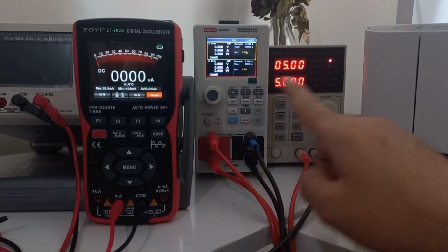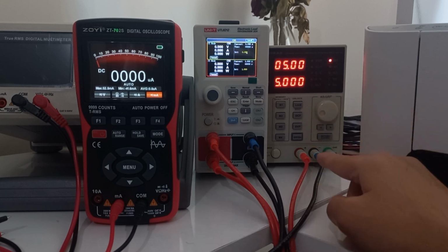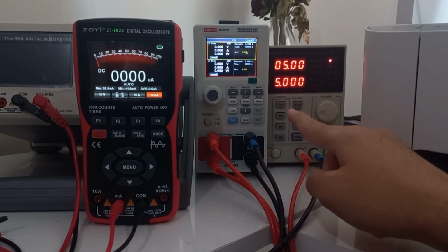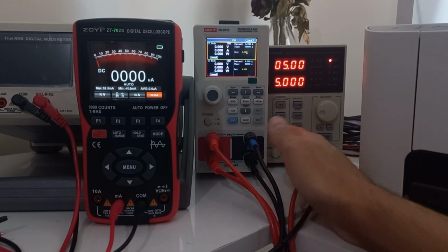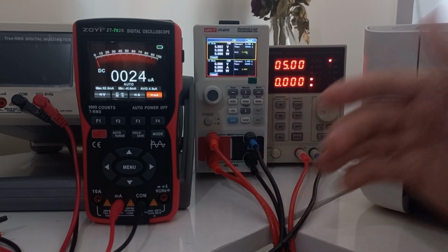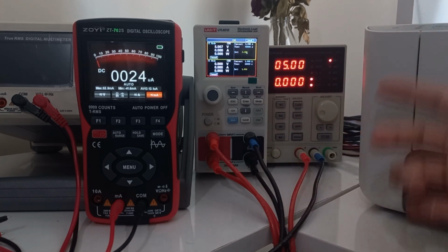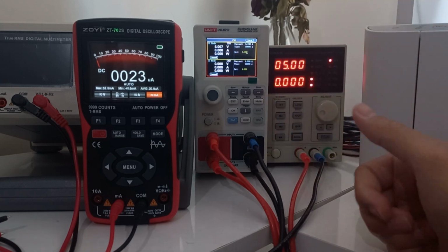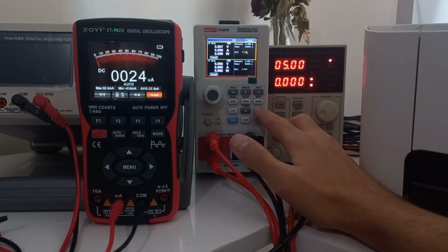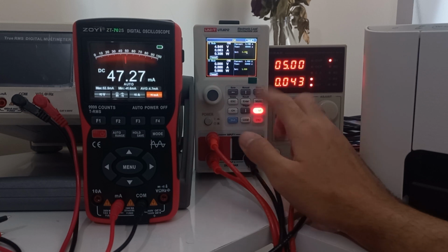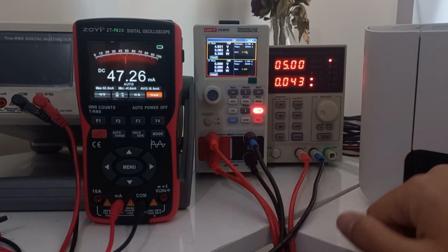Now we are going to check some current with this device. For checking any current, we have our power supply on the right side providing 5 volt at 5 amp, and our DC electronic load to take exactly as much current as we ask this device to take. Right now we are set for 50 milliamp. If I turn on this load, you will see that the measured current is almost exactly 50 milliamp.